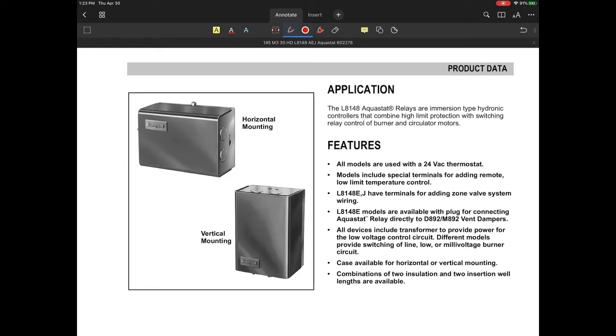So exactly what an Aquastat relay is: I always think of the Aquastat as the controlling device for the boiler. It's really a limiter, and in a lot of cases we call it a way to allow the boiler to warm up to a specific high limit temp. So that's part of its feature. And then there are also relays that can be in some of these, especially an Aquastat relay. They will include a relay that allows you to switch and control the burner as well as the circulator that's on there. So I want to hit up on some of these features that are important to recognize.